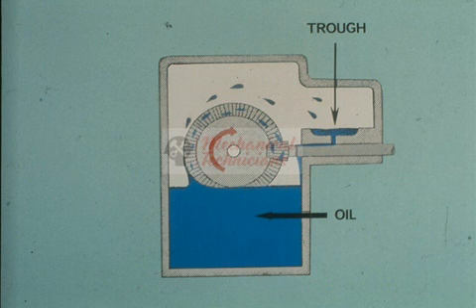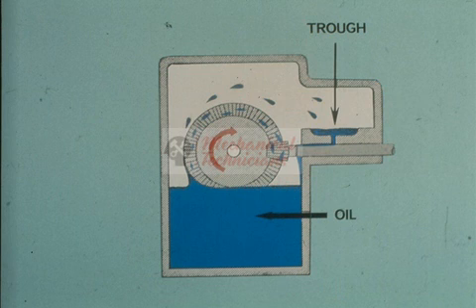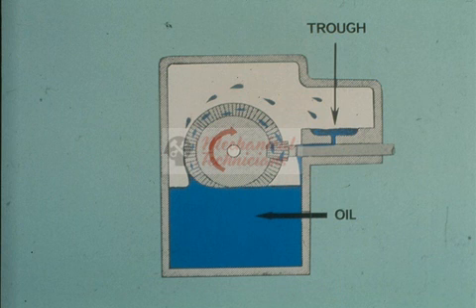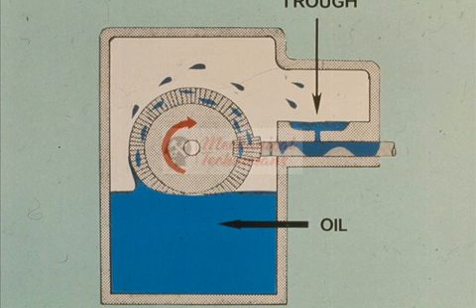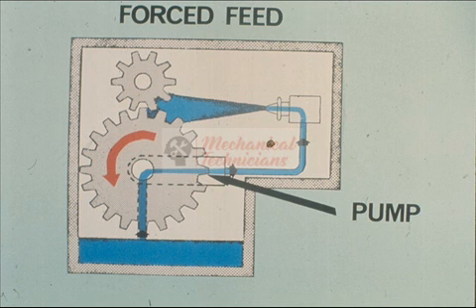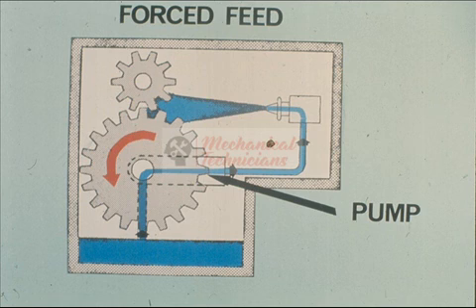Another factor vital to the smooth operation of all gearboxes is lubrication. Here is a typical right angle gearbox with bevel gears. The gears and shafts are being lubricated by a system called splash lubrication. The gear wheel picks oil up from the bottom of the gear housing and splashes it over both gears and into a trough, where the oil then runs down around the shaft, lubricating it. This system is often used in motor driven and small turbine driven gearboxes. Here is another very common lubrication system called forced feed, where a pump mounted on the low speed shaft draws oil from the bottom of the housing and sprays it onto the gears — usually used on larger gearboxes.